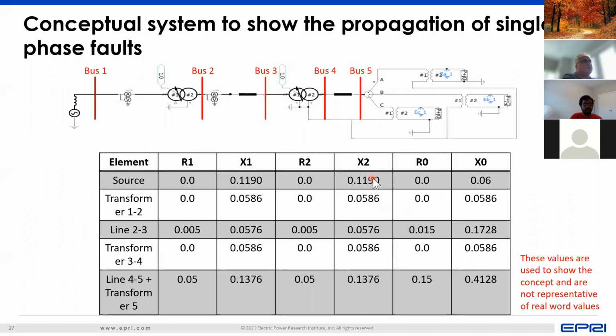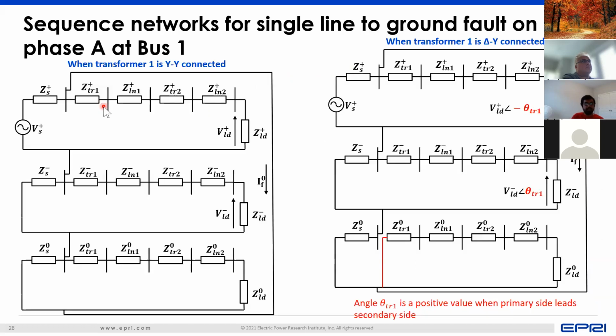If we consider a simple example of a system where you have a delta-star winding on these transformers at the substation, then it's important to understand how a single-phase fault propagates when it occurs at the transmission level. If a fault occurs at the transmission level, you can represent something called a sequence diagram, showing how the various phases of the circuit and the sequence of the circuit will be connected. When you have a transformer which is star-star connected, you have a closed circuit for zero sequence current to flow. But when you have a transformer which is delta-star connected, then you have an open circuit for zero sequence current, and you have a change in the angle that the load sees because of the phase shift between the delta and star winding.